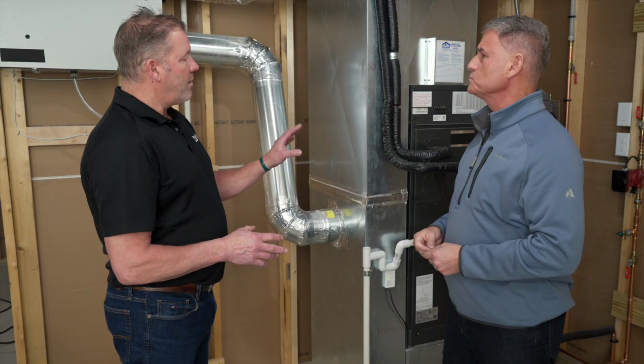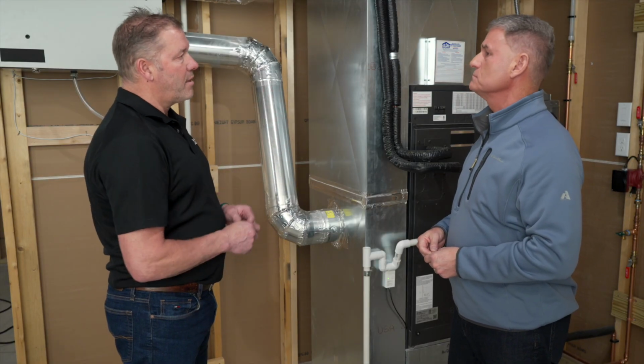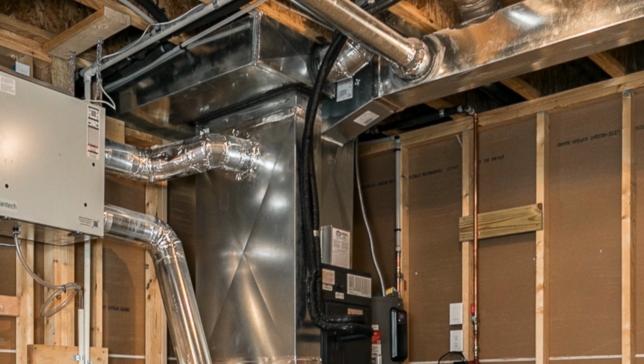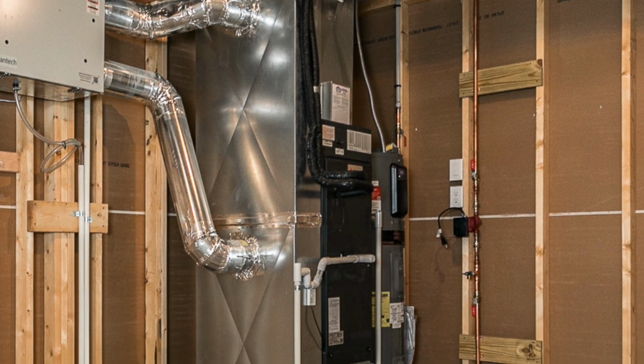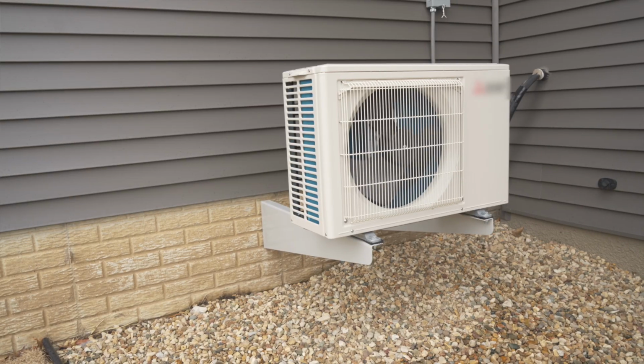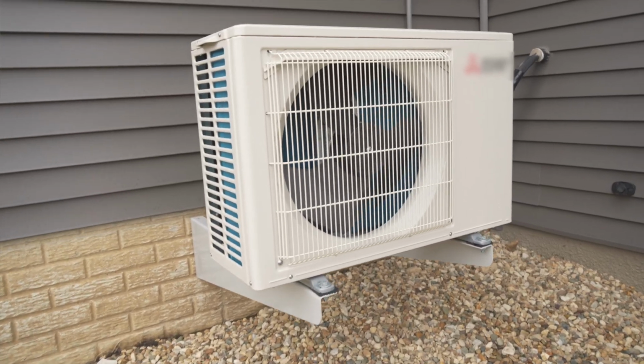We're in a new construction, so talk us through the installation of a heat pump here. This particular system has ductwork, just like a conventional heating and cooling system. We have an air handler here, and this air handler happens to have electric strip heat as our backup, and then we have an outdoor condensing unit. Again, we're in a new home construction, but it can also be a retrofit, correct? You can.